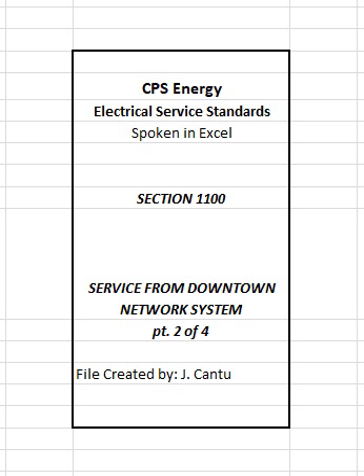2. No customer pipes, ducting, or wiring, except customers' service conductors, shall enter or pass through the transformer vault or room. 3. No other utilities such as gas, water, sewer, communication cables or customer systems of any kind shall be allowed to enter or pass through the transformer vault or room.